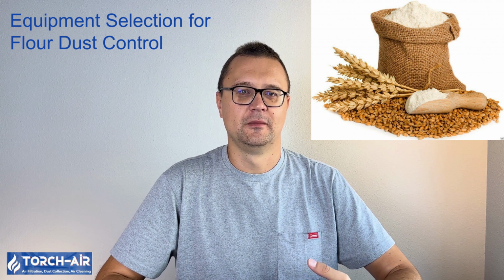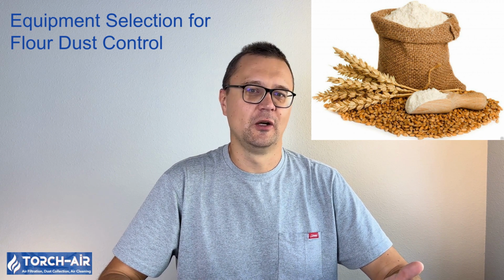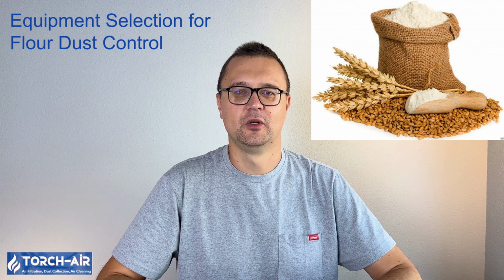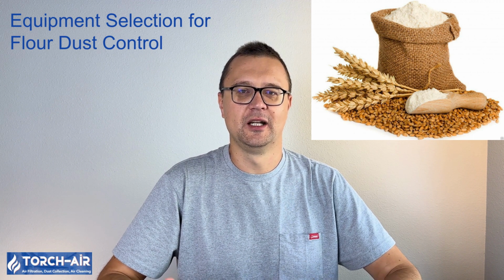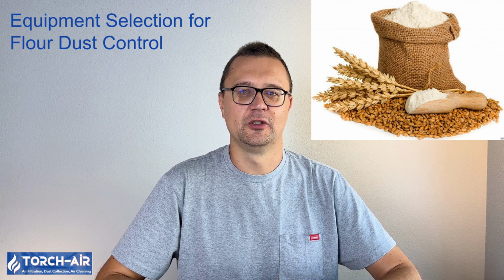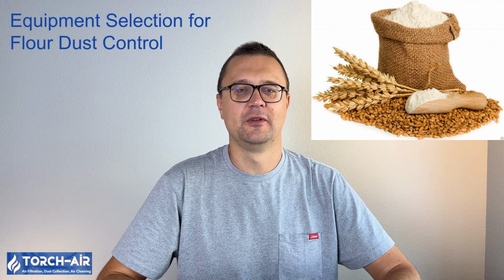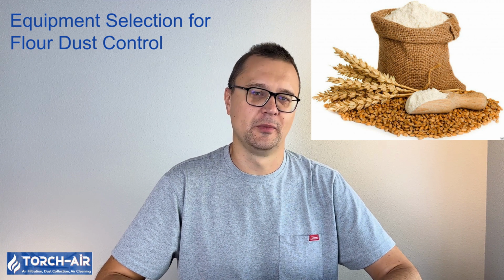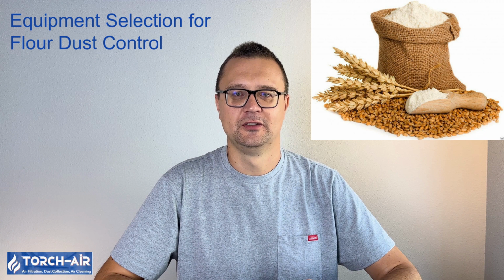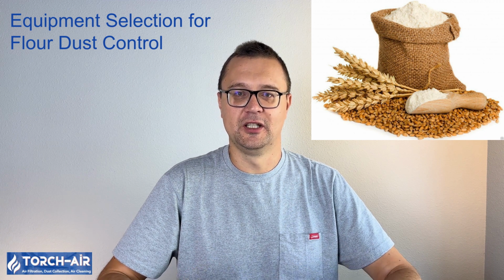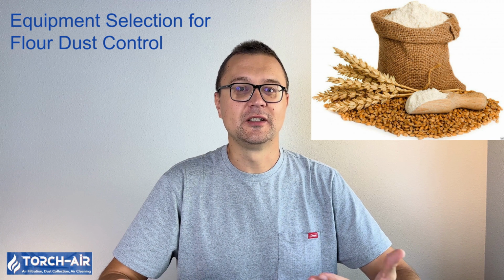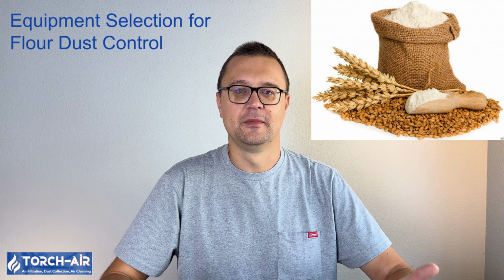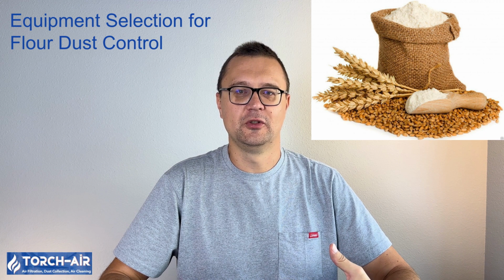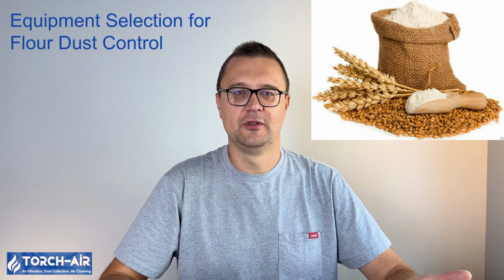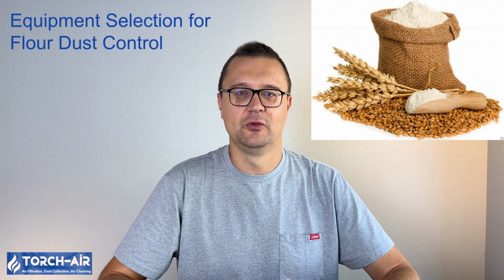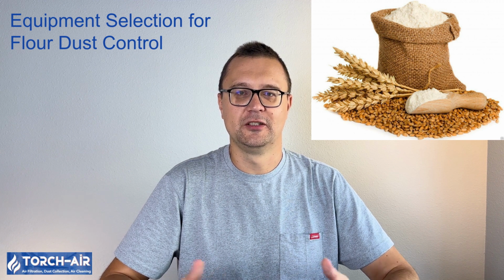Filter media. The type of filter media plays a huge role in how effectively flour dust is captured. Common materials used for filtering include polyester, good for general purpose filtration. Polyester filters are durable and effective for capturing fine flour dust. PTFE, Teflon, membranes. These are excellent for high performance applications as they offer superior dust release and chemical resistance. Nanofiber filters. These filters are designed to capture ultrafine particles like flour dust. Their fine fibers create an efficient barrier that prevents dust from passing through.